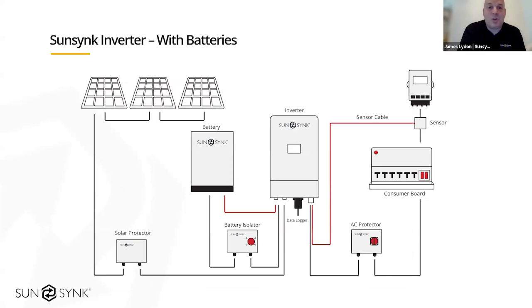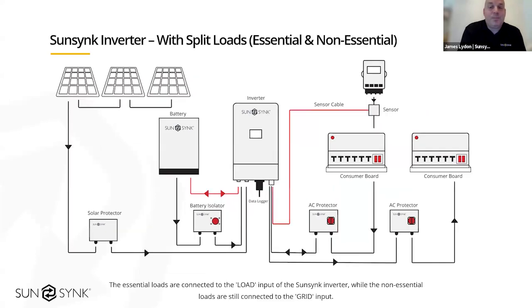So with batteries, obviously this is most common with our hybrid inverters. This is just showing a standard wiring diagram of a connected system with batteries. So this is with split load, so this is your essentials and non-essentials. This is back to what we spoke about at the beginning with the USPs. If there's a customer who is worried that they're in an area where there's a lot of power outages, we've got that dedicated output built into the inverter for UPS. So it's a complete uninterruptible supply. While it's on grid, that supply is always powered, so it'll work as a pass-through from the grid. And if there is a grid failure, it will work as a UPS.